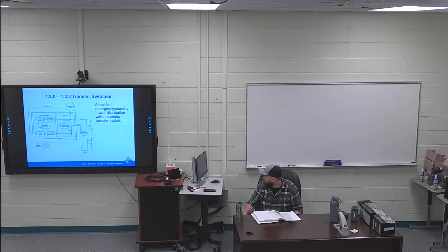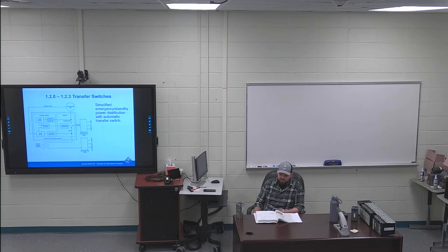Flipping over to page 8, that last paragraph before 123. The first sentence is highlighted: the sizing of transfer switches is based on the calculated continuous current. So remember from previous electrical classes, anytime you see continuous, you have to think it's usually calculated at 125%, in a manner similar to sizing the circuit conductors. So same thing, you're sizing this stuff up by probably 125% because it's considered continuous.